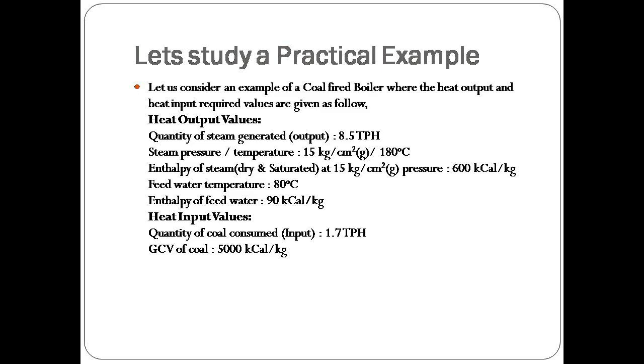Steam pressure and temperature: 15 kg per centimeter square is steam pressure and 180 degrees centigrade is the respective steam temperature. By the steam chart you can get the enthalpy value of steam at the respective pressure and temperature, which is 600 kilocalories per kg.